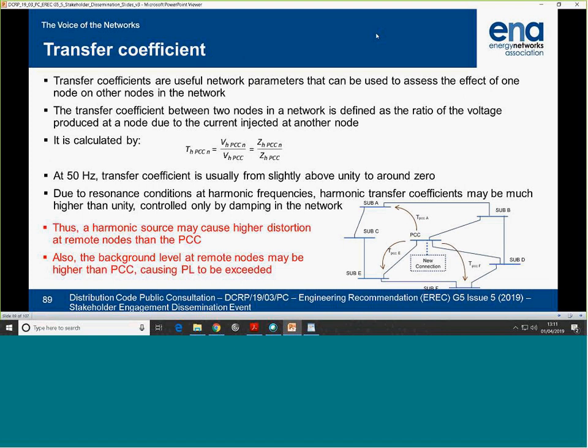In the assessment of stage 3, we use transfer coefficients. A transfer coefficient is a useful parameter you can use to assess the impact of a harmonic source at one point on the nodes in the system, the other substations. Basically, it's the same as a 50 Hertz transfer coefficient. It's exactly the same. You put it at the harmonic frequency. So it's the same concept as 50 Hertz.